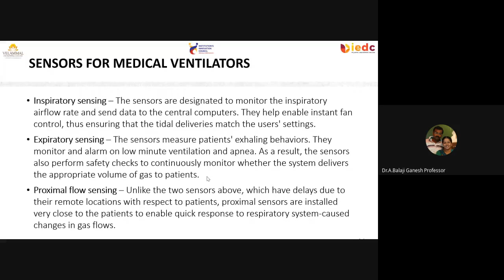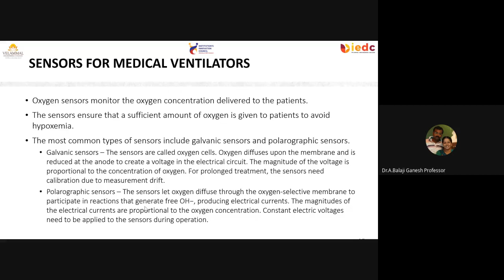The other sensors that are very much required for your ventilator system are the galvanic sensor and the polarographic sensor. The galvanic sensor is related to oxygen cell monitoring, whereas the polarographic sensor would detect whenever there is an oxygen depletion happening in the ventilating system. So if you want to contribute something for the ventilator, instead of creating your own ventilator, you can think about how to improve the performance of existing ventilators by adding this type of sensor.